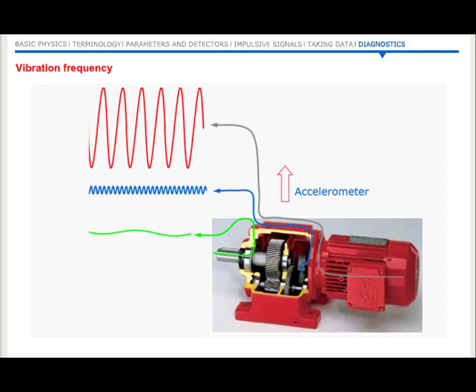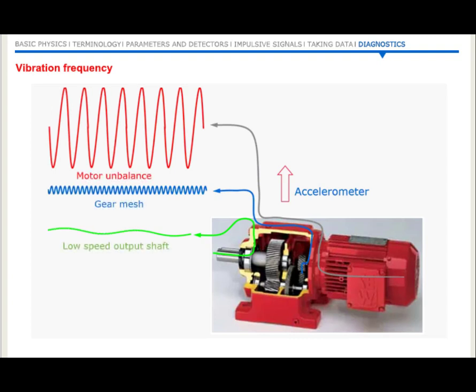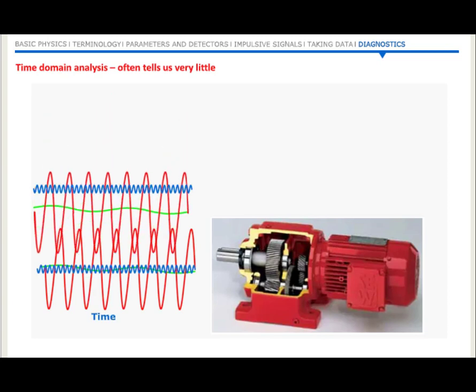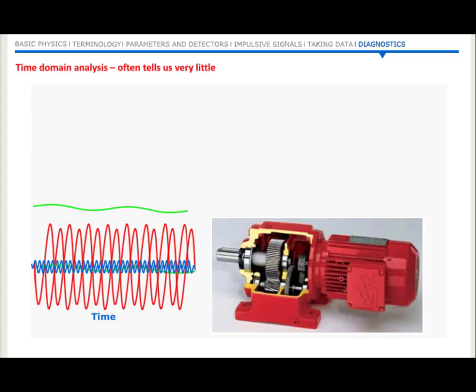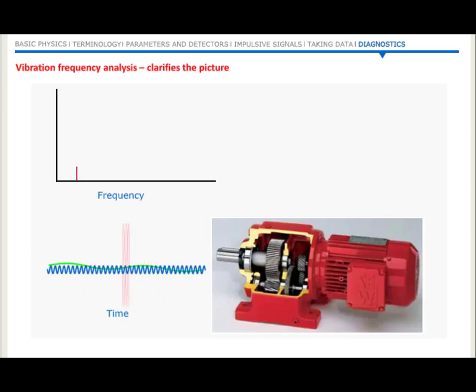Each and every rotating component will produce forces and vibration that relates to the frequency at which it operates, that is, its rotating speed. When we view the overall vibration in the time domain, it is usually very difficult to identify the individual components. However, when we view the signal in the frequency domain, the picture becomes much clearer. We briefly saw this view of the data earlier in the terminology module. The process by which modern digital instruments generate this view of the signal is called fast Fourier transform, FFT. For this reason, people often refer to the spectrum plot or frequency domain plot as an FFT.